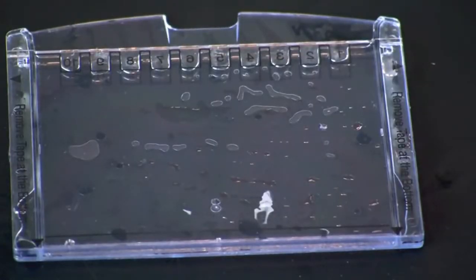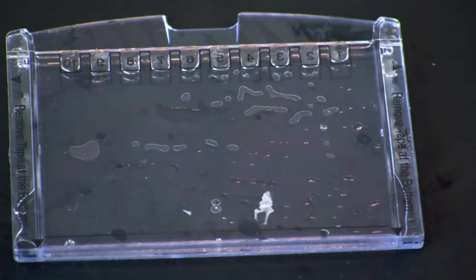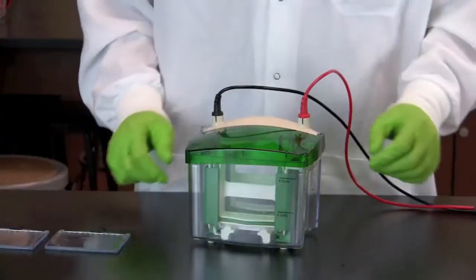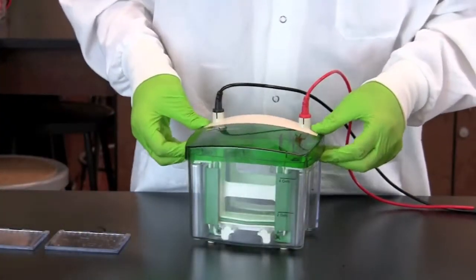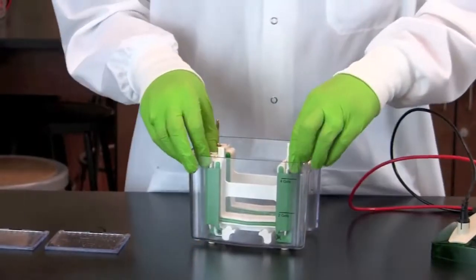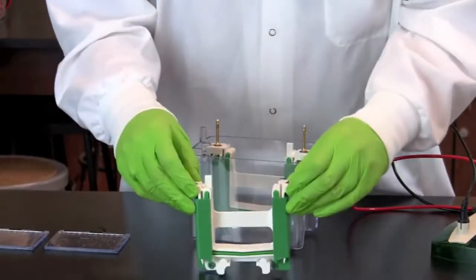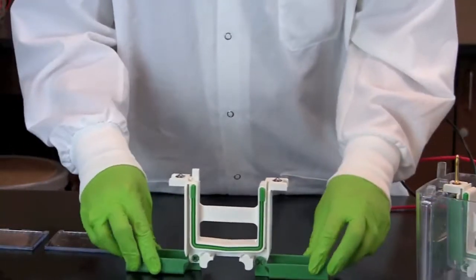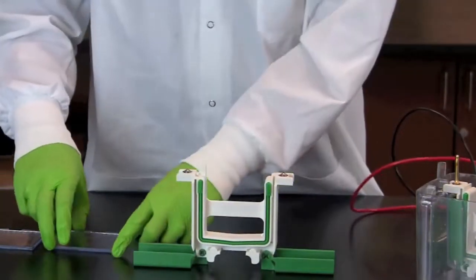Notice the gel has two plates, a short plate on one side and a long plate on the other. To set up the vertical electrophoresis system, remove the electrode assembly from the tank and open the green clamps. Place a gel into the electrode assembly with the short plate facing inward.